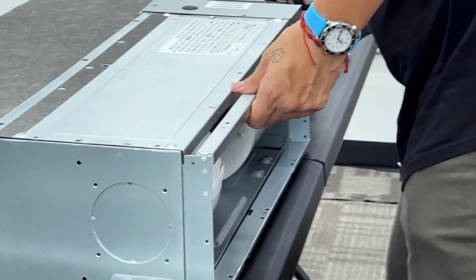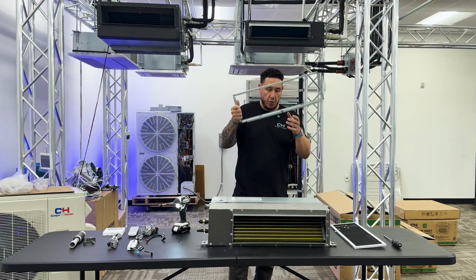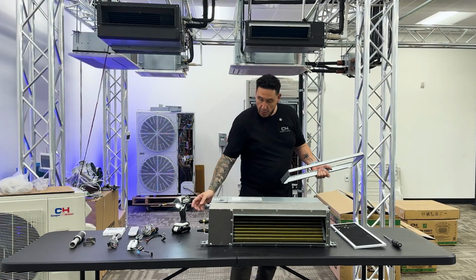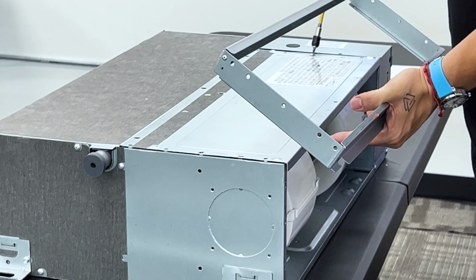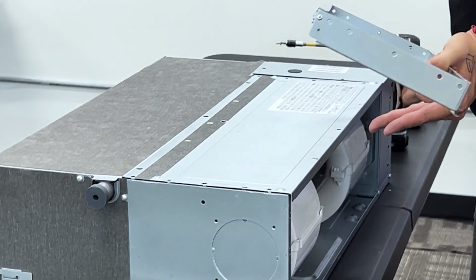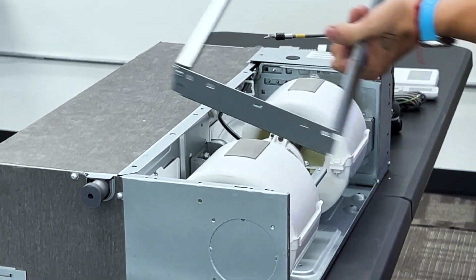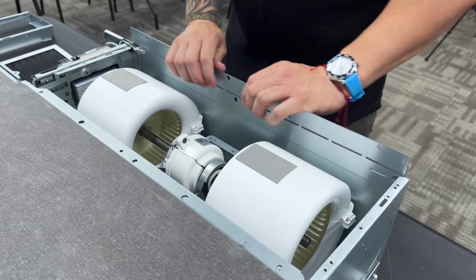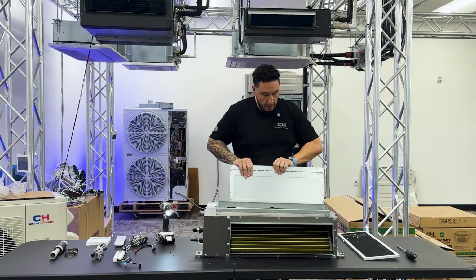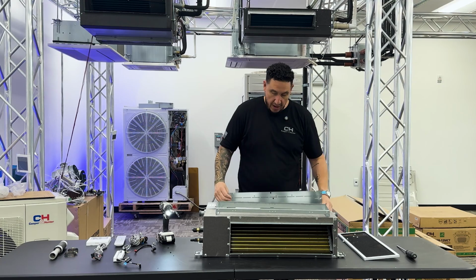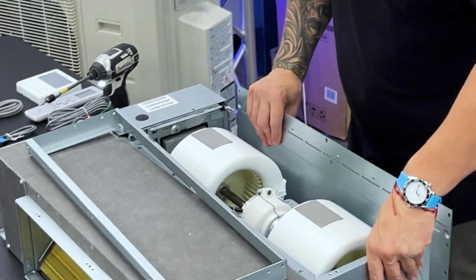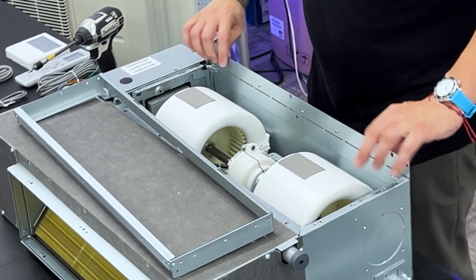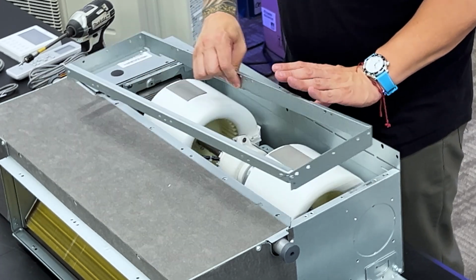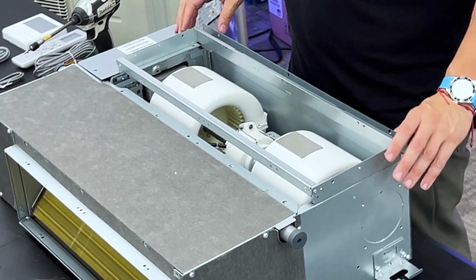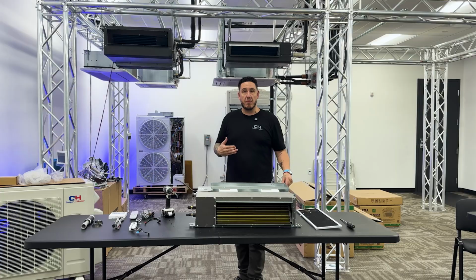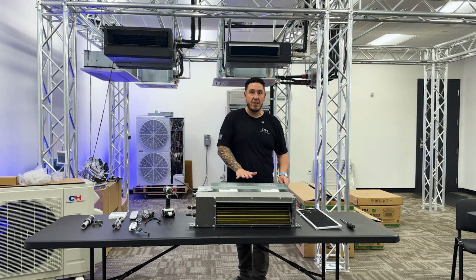Now what this allows me to do is remove my filter rack from the top of the unit, remove my panel. Right here on this panel, I have notches that you can bend. What you do is reposition this panel from the top to the back of the unit, line it up, bend these notches down, put your filter box right on top, and now look at that. I just changed my return from the back of the unit to underneath the system.